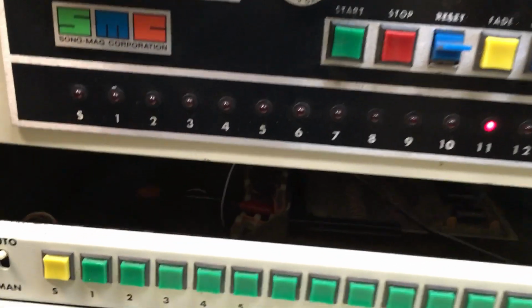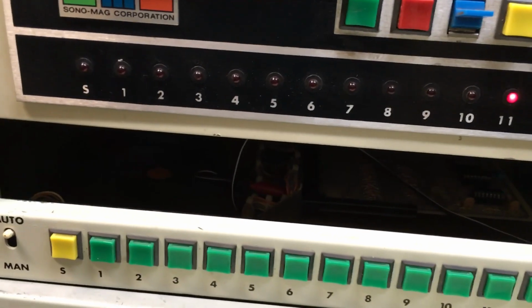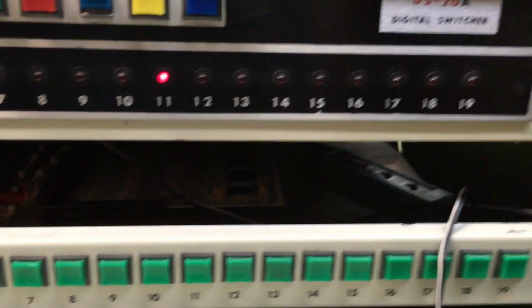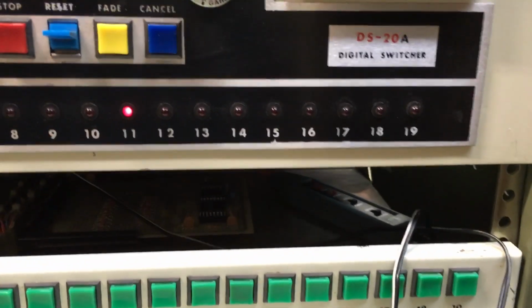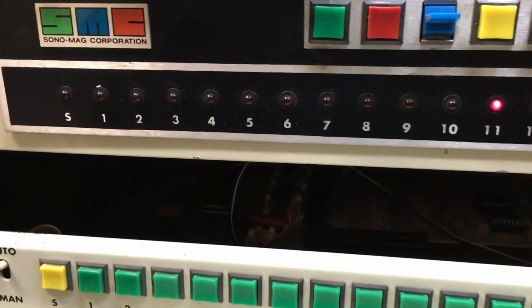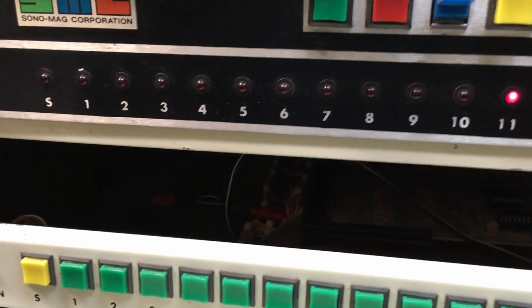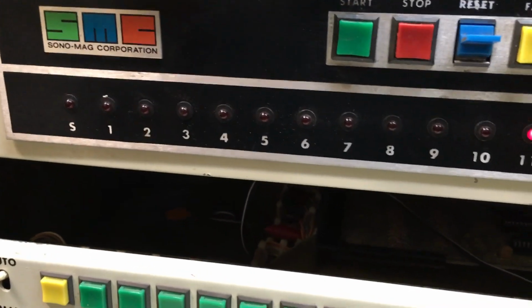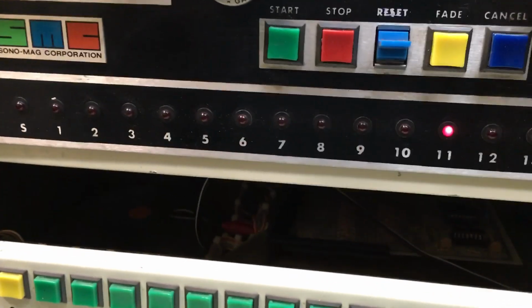So either source, the manual panel or the ESP-1, channels 10 through 19 still have every other channel being skipped over in the logic for some reason. 1 through 9 work perfectly as they should.